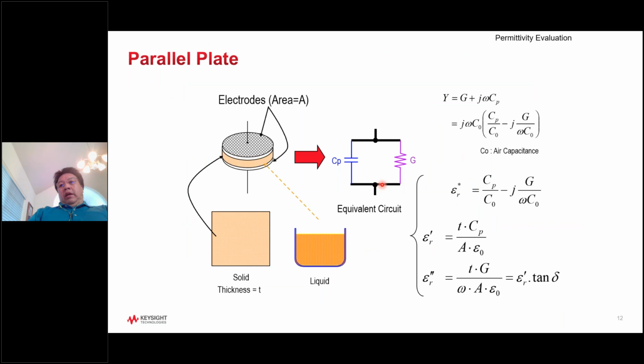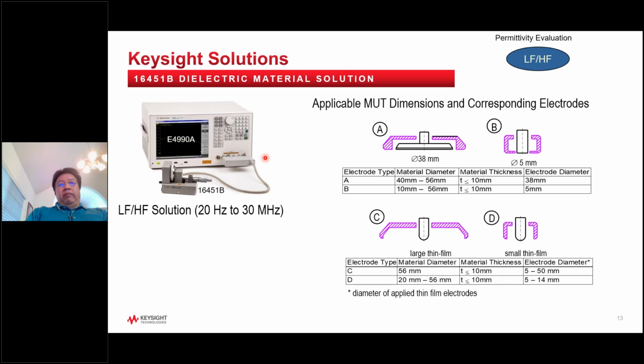So let me go into individual methods. Parallel plate: basically we are using two electrodes, for the top and the bottom. The yellowish color is your sample. When we sandwich the sample between these two electrodes, we measure the capacitance and admittance, and from that we can calculate the permittivity using this formula. Of course, with this method you want to minimize the air gap. The air gap introduces measurement error. So when you prepare your sample, you need to consider the flatness and make sure the material is flat all the way across.